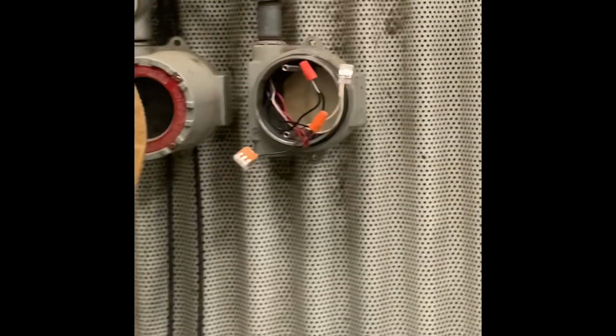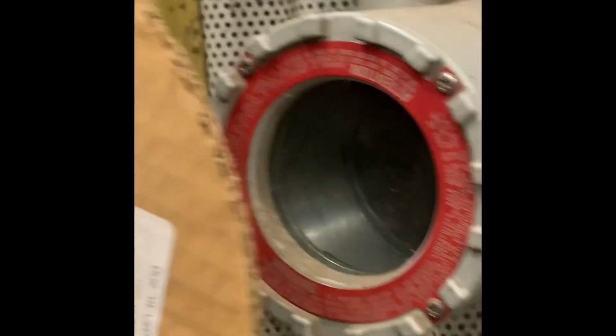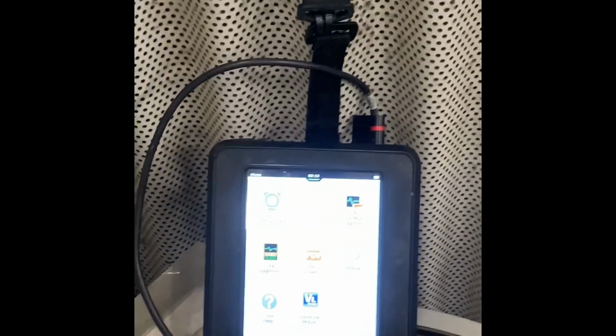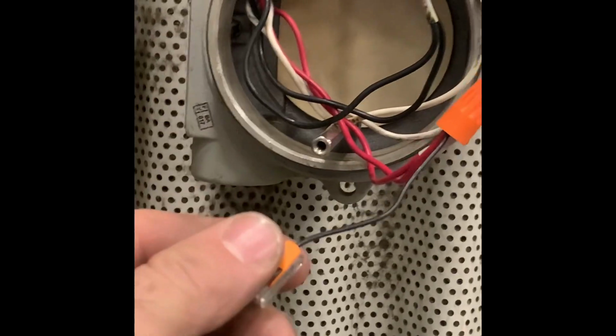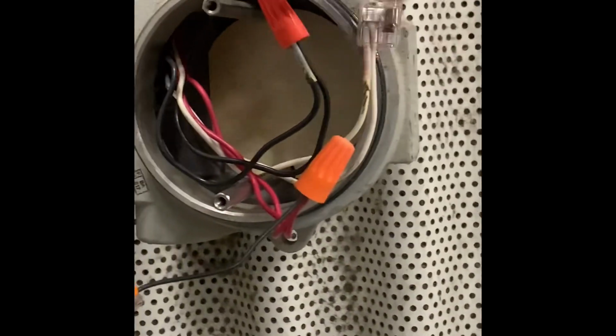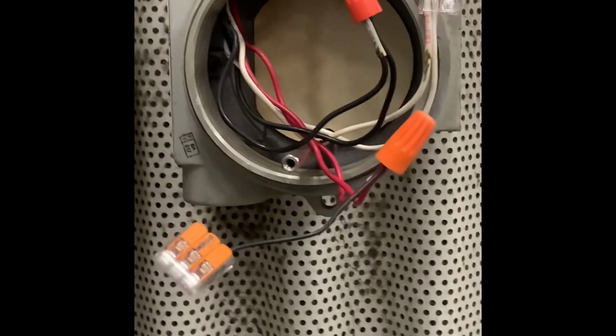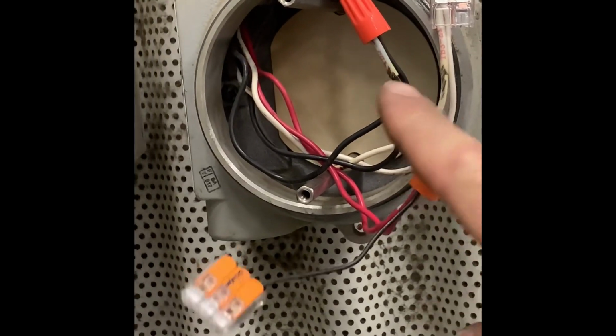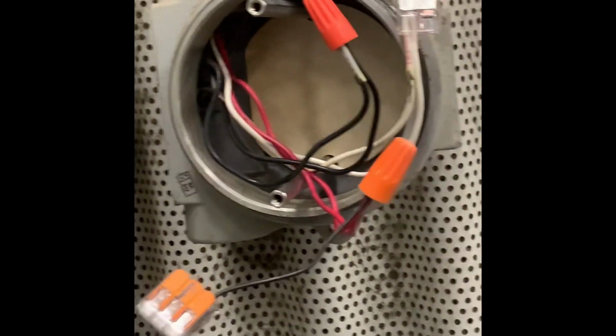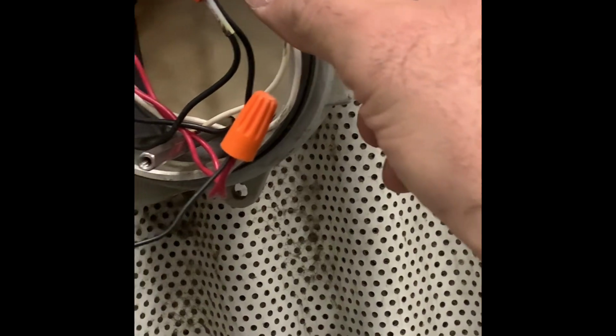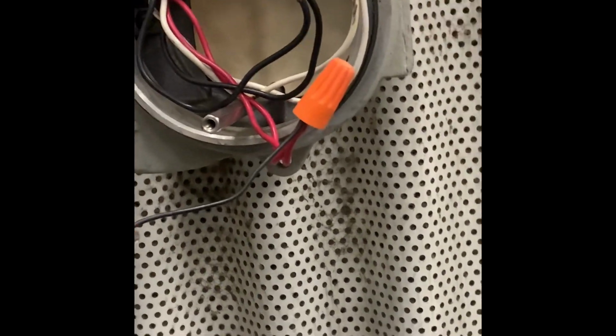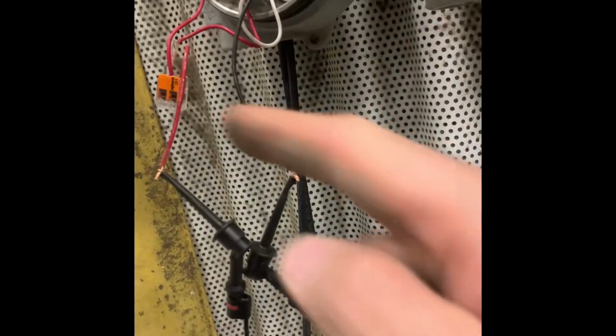Hey guys, so I'm going to be calibrating this Draeger gas detector that we have, and here's the wiring. I got to hook up my HART device to it, my Trex unit. So red to the positive 24 volt and black to the signal, which is white. And I don't need a 250 ohm resistor between the two, because it's going back to the PLC. So I can communicate to it without having to put that resistor in there.